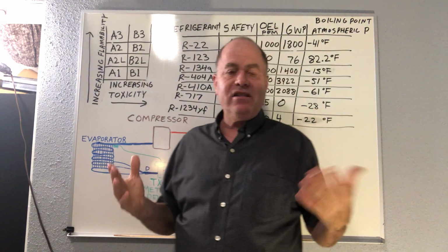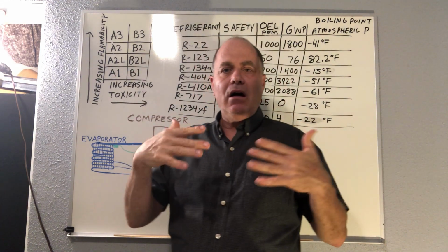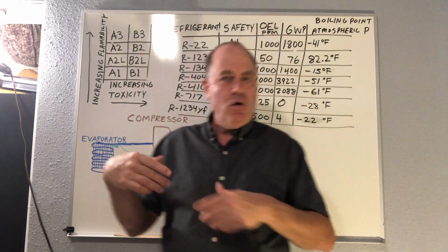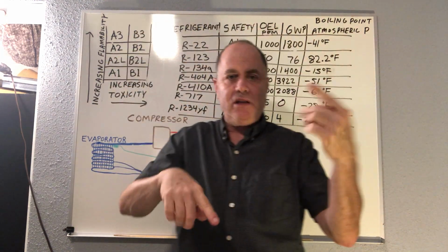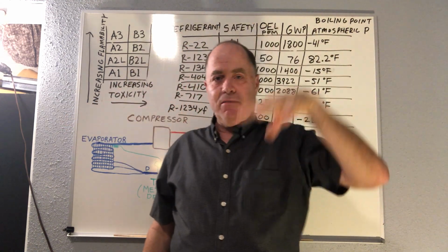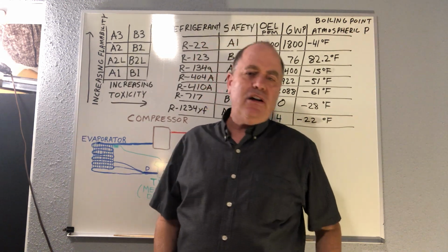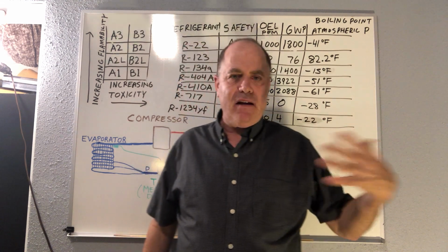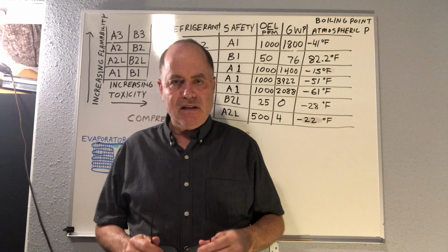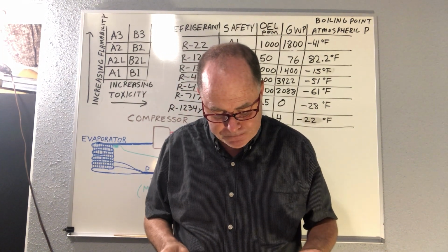Now, a lot of systems, if you just remember 150 and you put that in for most systems out there, that's okay. And a lot of times I'll look more at the low side test pressure, because once you put dry nitrogen, it tends to go to the whole thing. So if you're just focused on the high side one, that's a much higher number, which the low side may not be able to handle. But in reality, if you go a little bit above that, normally it's not going to have any unsafe condition, but just use that as a guide. We're not really supposed to exceed those test pressures, okay?